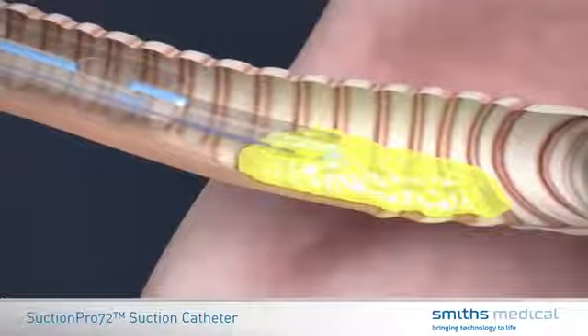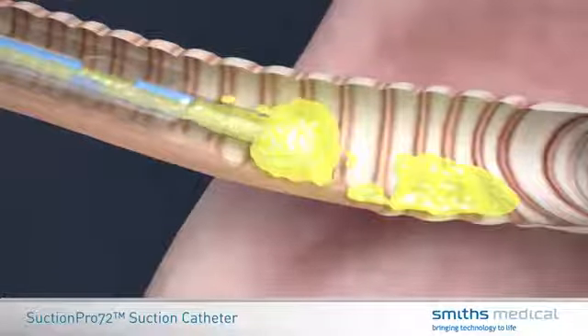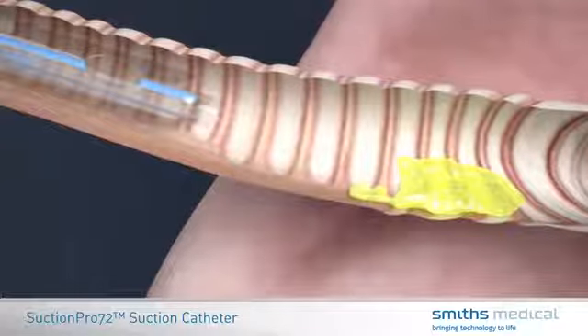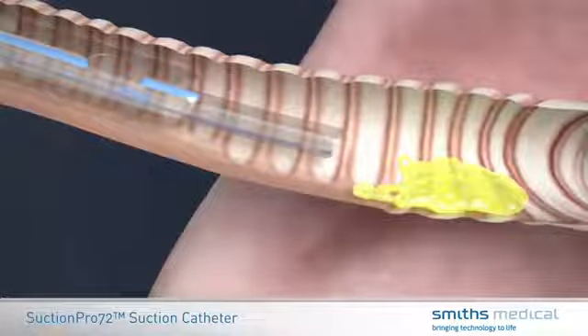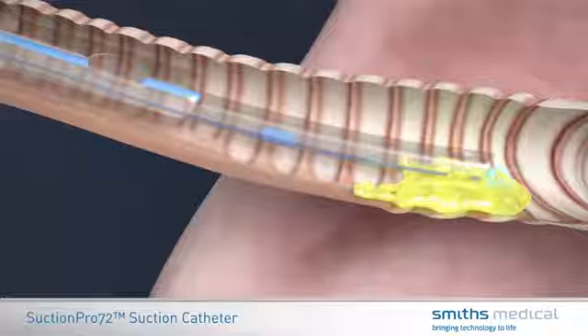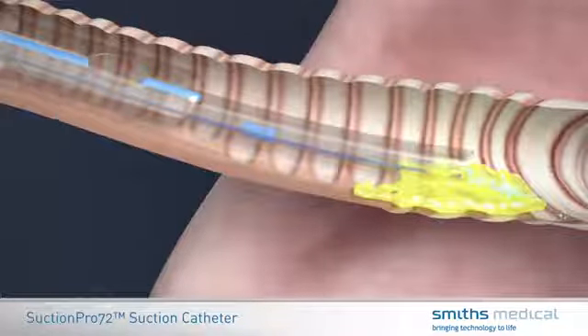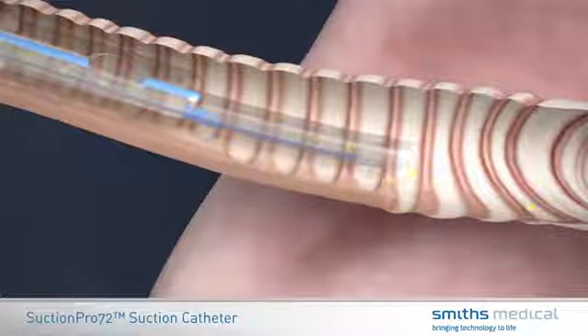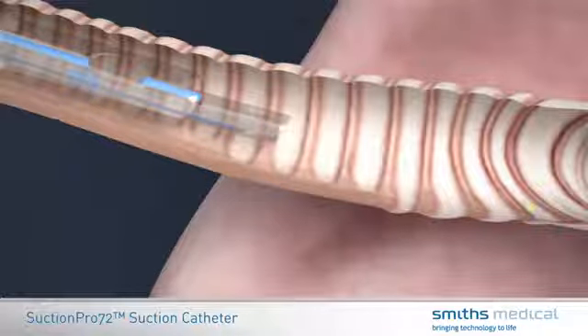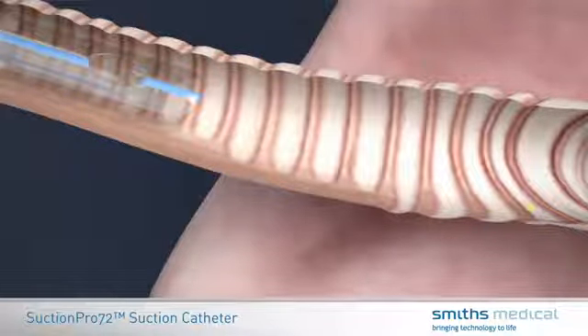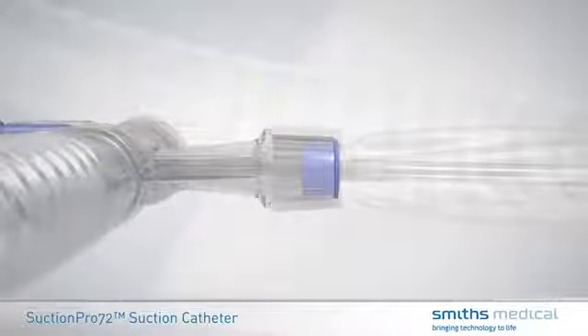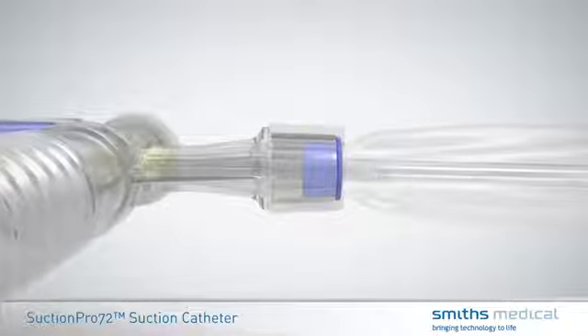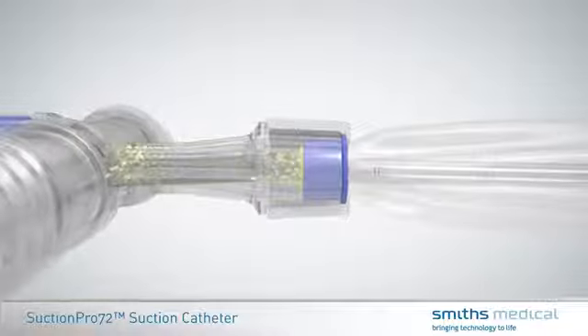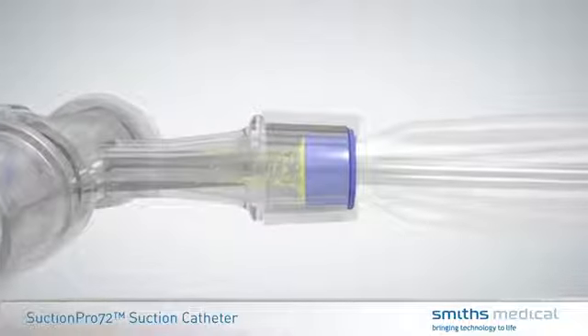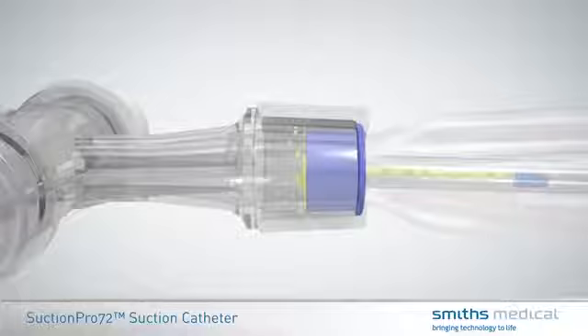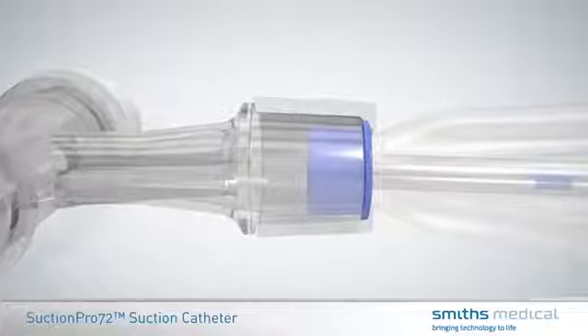The dual lumen catheter version allows for the pinpoint application of saline lavage directly onto thick and tenacious airway secretions, reducing the introduction of excess irrigant and improving the clearance of fragile airways. The dual lumen lavage technique also minimizes the risk of rinsing biofilm from the walls of the artificial airway. A robust wiper seal designed to clear away secretions from the outer side of the catheter also ensures no airway pressure is lost due to leakage into the catheter sleeve.